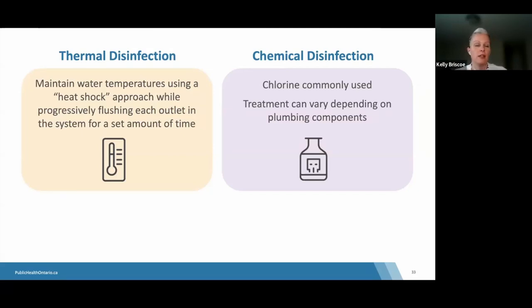You need to ensure that the system materials and equipment are designed and constructed to withstand high temperatures. You also need to be aware of locations of any temperature mixing valves, because thermal disinfection won't disinfect past that point of the mixing valve or downstream from the mixing valve. There's also the potential to dislodge particles from piping or plumbing walls, which can lead to clogging.